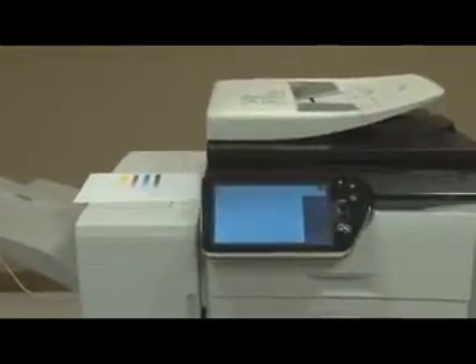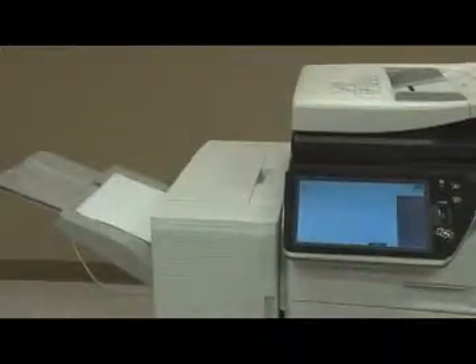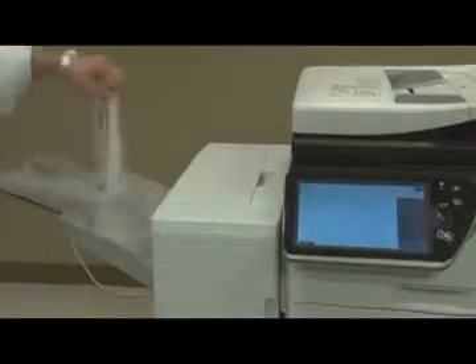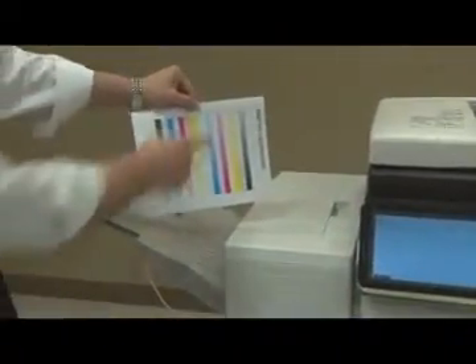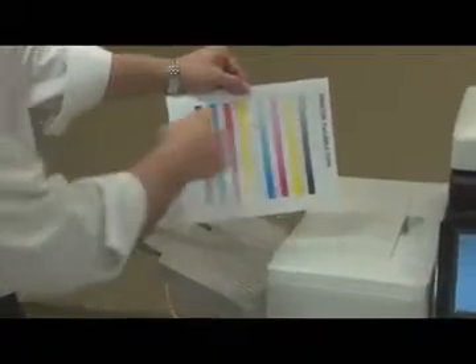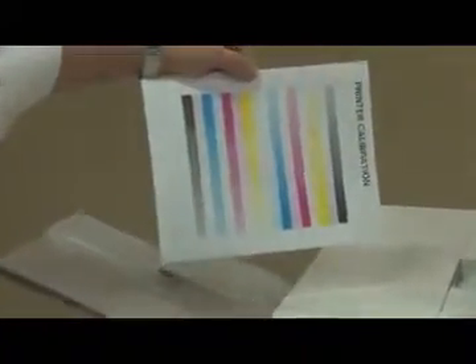In the display, it's asking us to confirm the patch, which we just did, and then select the execute key again. So we're going to select execute. And what that'll do is it'll print out the printer calibration test patch, or test pattern. So this is our printer calibration. Because it says printer calibration, it has the same pattern and the same thin line along the lead edge.